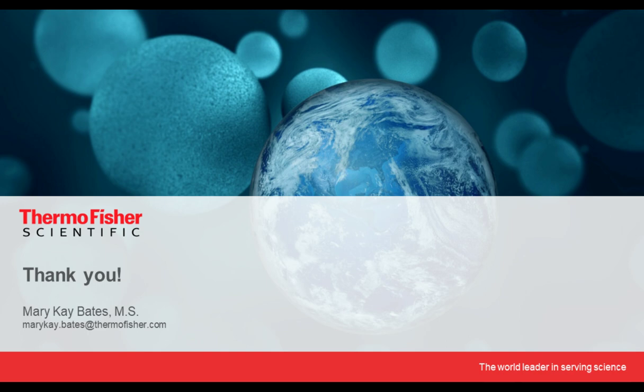So the National Institutes of Standards, and I can't remember what the T stands for, might be temperature. So you want a calibrated secondary thermometer, and even those can vary by 0.1 to 0.2 to up to 1 degree. So make sure you use a secondary temperature probe that you know the calibration on, so that if your incubator says 37 degrees and your secondary temperature probe says 38 degrees, it doesn't mean the incubator is wrong. So you need to use a secondary temperature probe that has been calibrated, and what the plus or minus variation on that secondary temperature probe might be. But yes, so the idea is use a secondary temperature sensor and put that in the incubator chamber.